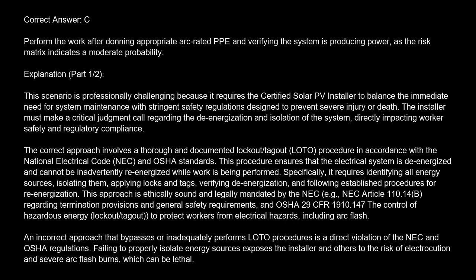established procedures for re-energization. This approach is ethically sound and legally mandated by the NEC Article 110.14(B) regarding termination provisions and general safety requirements, and OSHA 29 CFR 1910.147, the control of hazardous energy, lockout/tagout, to protect workers from electrical hazards, including arc flash. An incorrect approach that bypasses or inadequately performs LOTO procedures is a direct violation of the NEC and OSHA regulations. Failing to properly isolate energy sources exposes the installer and others to the risk of electrocution and severe arc flash burns, which can be lethal.